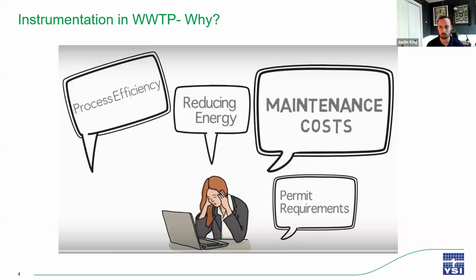Next, and what I think is the most important part of online process instrumentation, is that it can be used to control the process. So this constant 24/7 data flow can be used to control different processes. And the outcome is that it makes the process more efficient. And by doing that, we can reduce energy cost and we can reduce chemical dosing cost and tons of other costs throughout the plant that you wouldn't typically associate with instrumentation in general. So for example, we can use dissolved oxygen sensors to control the aeration basins and the blowers, and create the most efficient aeration process possible, possibly saving thousands of dollars throughout a year in energy cost for running those blowers.